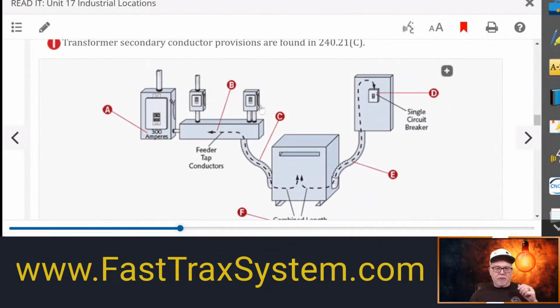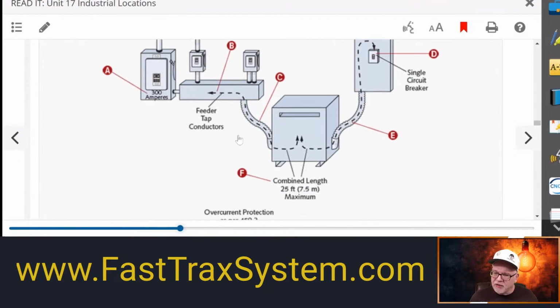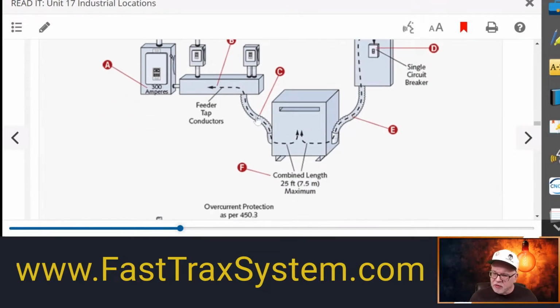So this is how we would size it. Again, as a synopsis, these conductors right here have minimum sizes they have to be if you're going to use this tap rule. Could be more based on the rating of the devices that you're terminating into, and the transformer's output and all those types of things. But we know what the minimums have to be. Could be greater, all right?